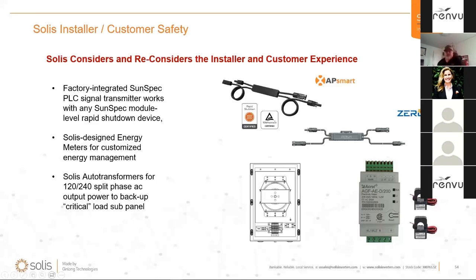Like I said, you've just got a one-box solution with the hybrids. The transmitter's already in there. So as soon as you apply AC power to our inverters, you are transmitting a signal to either APsmart or Zerun type, or what we call SunSpec PLC type devices, or you can use Tigo, or like I say, none at all. But you're likely going to need the hybrid inverter itself, the rapid shutdown devices, your PV array, and if you want to do backup, you're going to need your autotransformer, and Solis has one that can do 120/240 split phase. And you're also going to need a small meter that comes with the hybrid inverter in the same box.